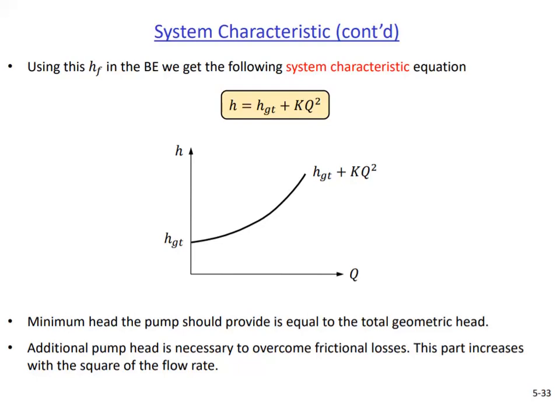Combining this KQ squared relation with the geometric total head, we obtain the system characteristic equation that we need. We can plot it just like the fundamental pump curve. In a sense, this is the demand curve, showing how much head the system requires from the pump at a given flow rate. The required head increases with the flow rate because the losses increase with the flow rate.